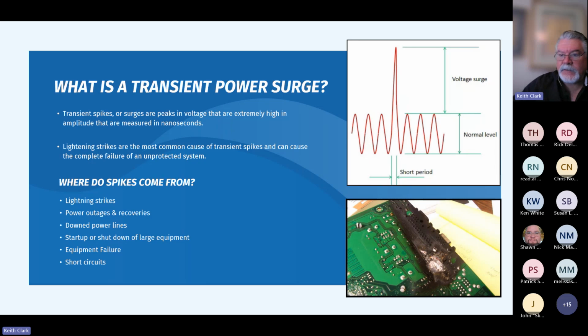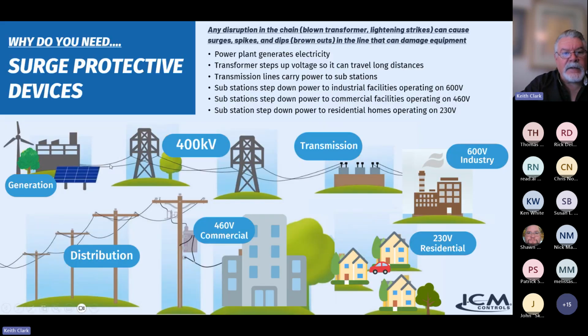Equipment failures, short circuits, a whole variety of things can happen. And just a quick overview of how power is generated and pushed downstream. There can be issues in any phase of this energy chain that can cause spikes and irreparable damage. Power generation stations, and there's a variety of different ways they do that, from hydroelectric, and now we've got wind, solar, a lot of different ways to generate power. They actually have to step power up at that point so that it can travel long distances across the countryside. You see the big metal power poles out there across the country landscape, sending power from one city to the next. They need extremely high voltage so it can travel those long distances.